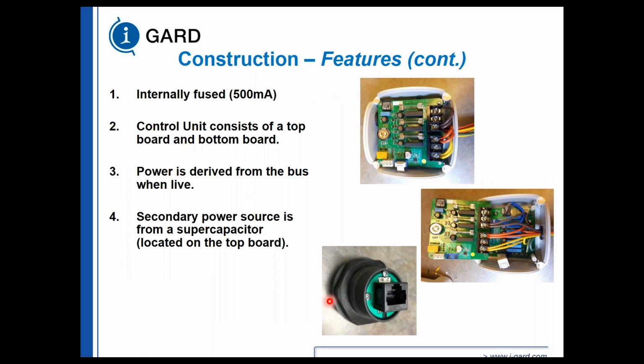So this product is internally fused at 500 milliamps. The control unit has 2 boards, top and bottom board. Power is derived from the bus, so no additional power supply is necessary for this unit to be working. We have 1 unit that works from 120 volts to 690 volts. However, it's only UL listed and CSA approved to 600 volts. But it works on 690 volts. The secondary source is charged from a supercapacitor right here. So we charge the supercapacitor, and this is our secondary source that we use to verify the absence of voltage and test our meter to a known device or known voltage.